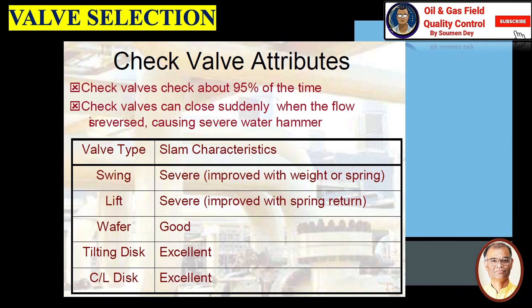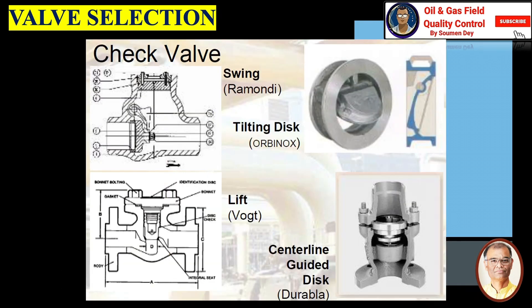Regarding slam characteristics by valve type: swing type is severe, improved with weight or spring. Lift type is also severe, improved with spring return. Wafer type has somewhat better slam characteristics. Tilting disc and centerline disc types have excellent slam characteristics. You can see the different types of check valve: swing type at top, tilting disc at top right, lift type at bottom left, and centerline guided disc at bottom right.